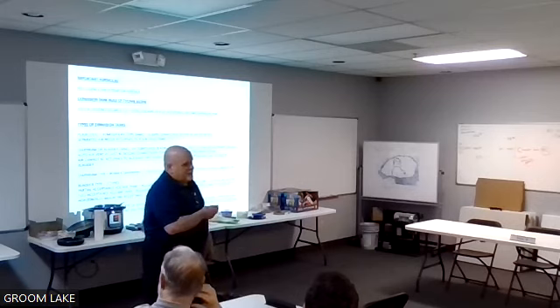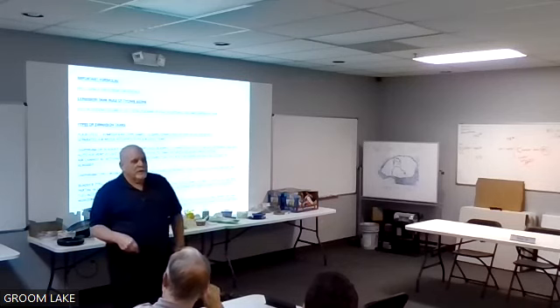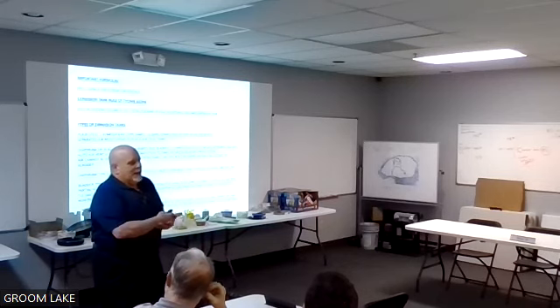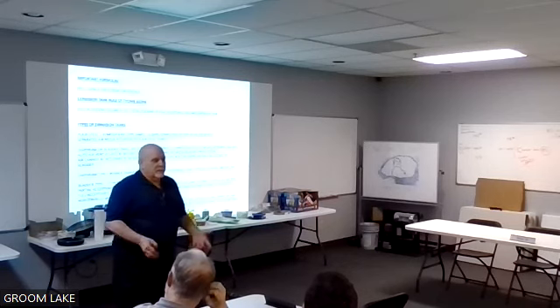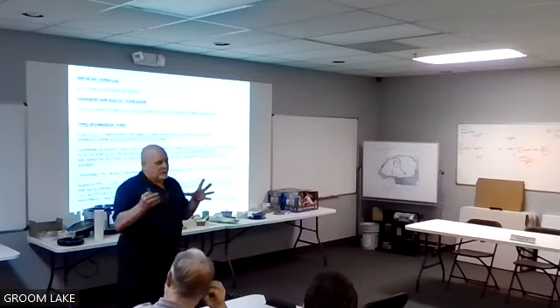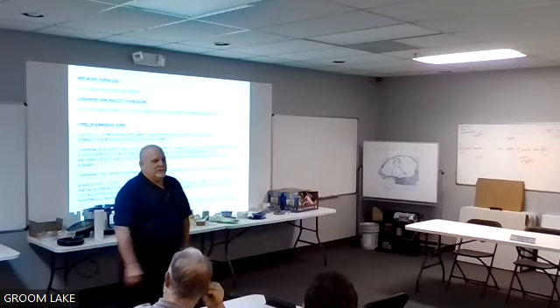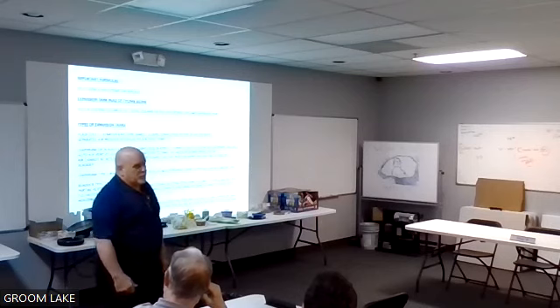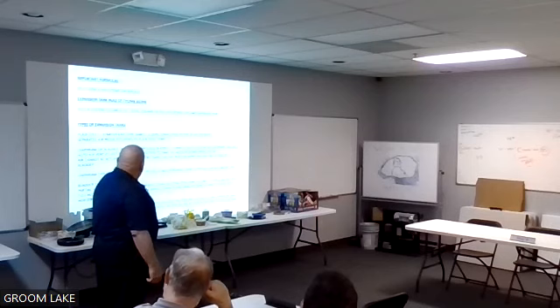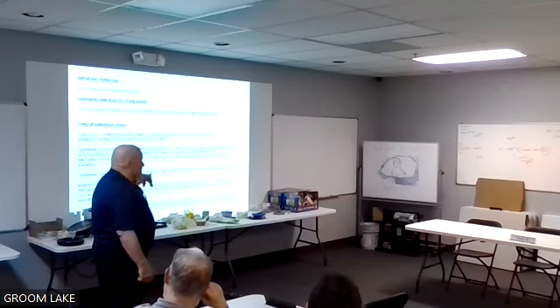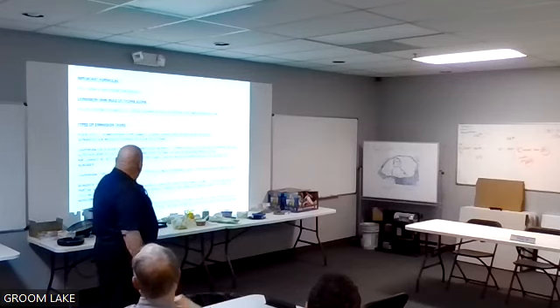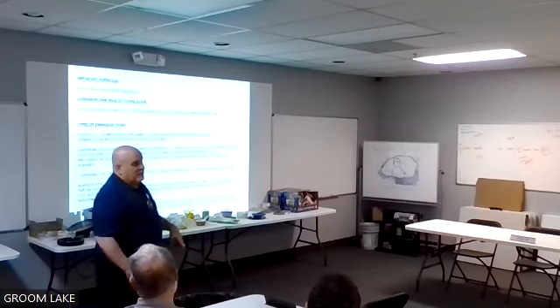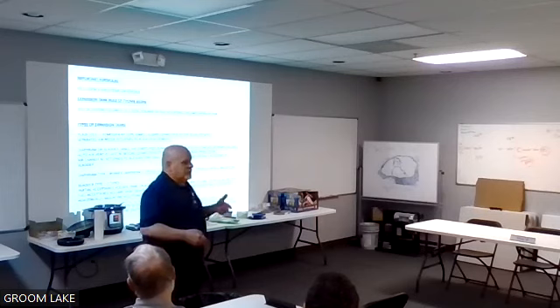Most of the diaphragm tanks are throwaway tanks. They're cheap, but if you rupture that diaphragm, you have to buy a whole new tank. There's no way to replace that bladder. That bladder is fixed, and it's junk after it ruptures. Then you have the partial acceptance volume tanks and the full volume acceptance tanks. And we'll get into this. You'll see pictures of them.